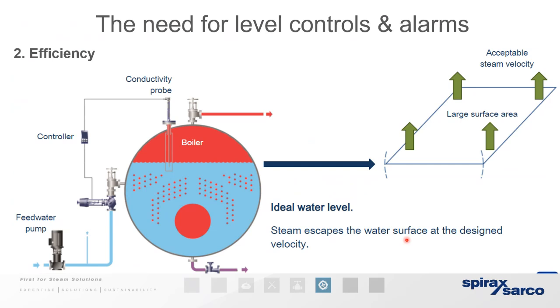The reason they're smaller is that they become more efficient. It means that, because of the limited capacity held here, they need to be able to act fast. So modulating pumps and the various controls that Alvin was touching upon all help the boiler respond quickly.